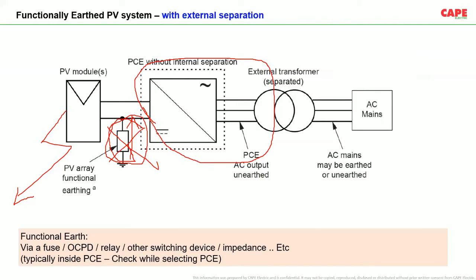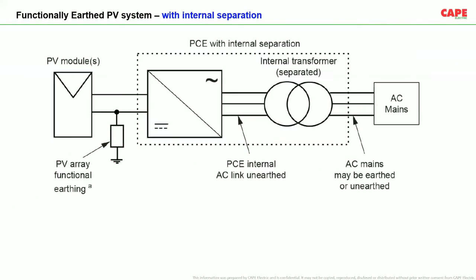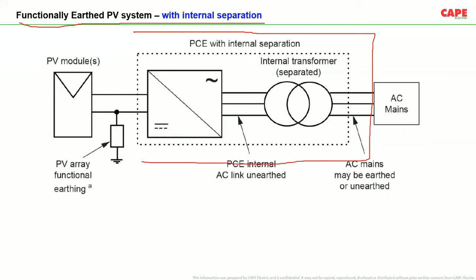So as I said, the methods implemented in solar PV are a little bit different than what we generally do for AC applications. So we have to be very careful. This one is a functionally earthed PV system with internal separation. That means the PCE has a transformer inside. The electrical isolation happens internally within the power conversion equipment. Here also you can see the functionally earthed system.